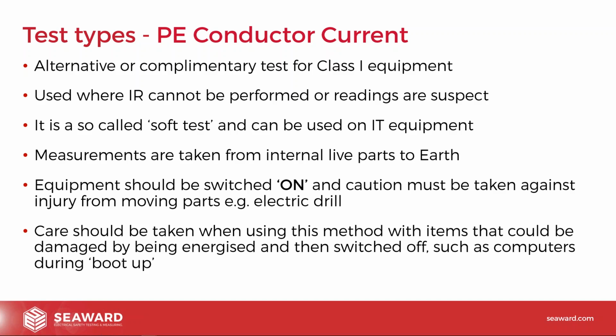It's something that we would generally recommend doing an insulation resistance test first, to make sure there are no obvious shorts or anything like that on the lead, before you do this test. But then you've got to be careful while you're doing the test, especially if it's equipment in an unknown condition. If we don't know this equipment's safe to use, we're actually putting mains into it and turning it on to get it to run to measure the leakage. That said, it is a very accurate test. It will give you a real world picture of the leakage of that equipment.